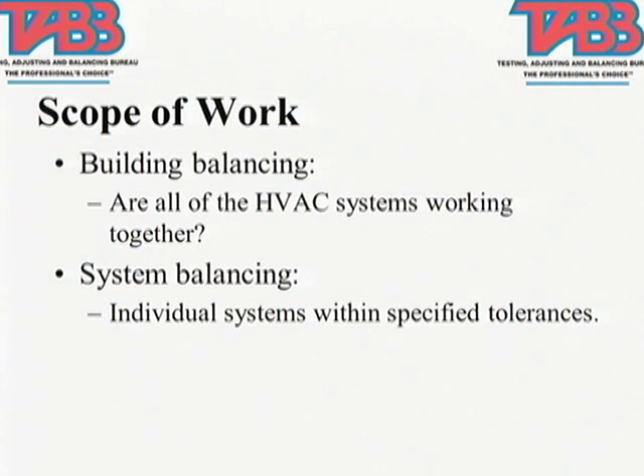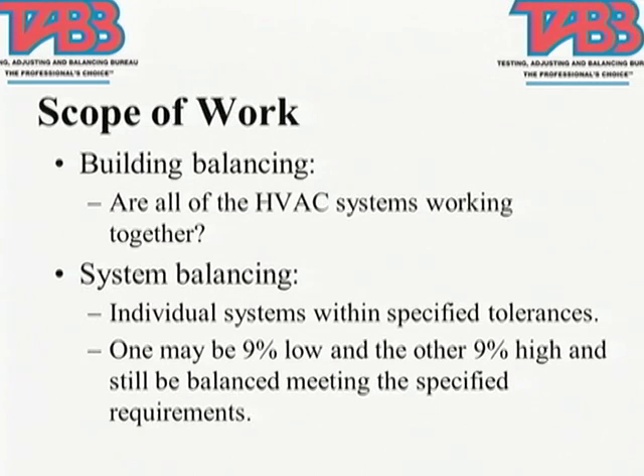It's individual systems within specified tolerances is all the balancer is doing. A good example is one might be 9% high, one might be 9% low, and you have an 18% difference, and that would explain the 20% air that's flowing into your face when you're walking inside a building. Like, why is it so windy in here? They don't worry about that scope. They're only balancing to those specifications, to those systems.